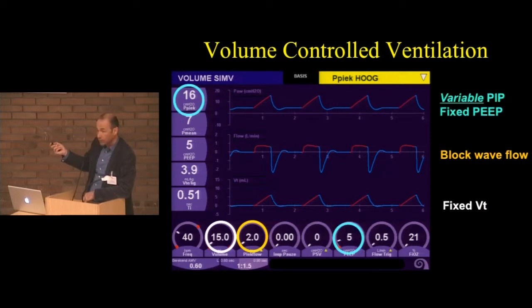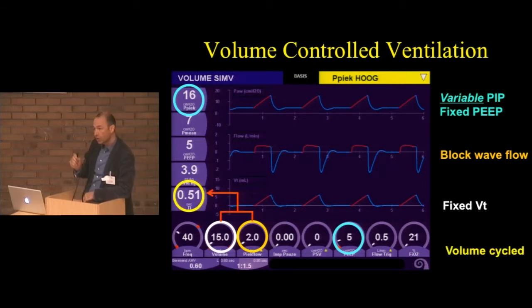And the actual peak pressure is variable now, depending on the compliance and the resistance or the spontaneous effort of the patient. And finally, this is a volume cycle mode, which means that the end of inspiration will start as soon as the tidal volume is delivered to the patient. And the time depends on the flow you set as a clinician. More flow means you reach the tidal volume sooner, so you get a shorter inspiration time. And of course, it depends on the volume itself. So this is basically a different approach of ventilating our patients.